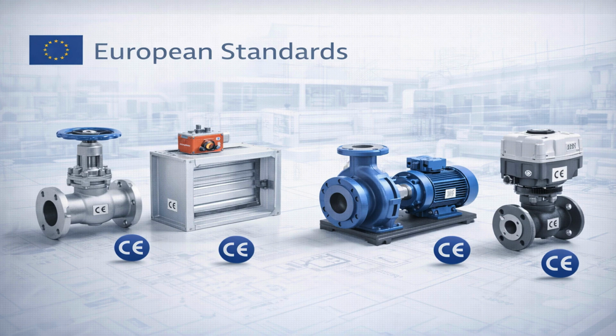These standards are critical for components such as valves, dampers, pumps, and fire-rated components including smoke and fire dampers. For this equipment, site testing is not enough. Their performance depends on factory controlled testing and certification. European standards ensure something very important. That is, what is tested in the factory is exactly what gets supplied and installed on site. This protects projects from unverified or lookalike products, inconsistent manufacturing quality, and equipment that performs well on paper but fails in real operation. That is why authorities, consultants, and inspectors often ask for EN test reports, CE marking, and third-party certification, because EN standards provide confidence that the product meets minimum safety and performance benchmarks. The installed equipment is not an experiment. In short, European standards protect the project before installation even begins.